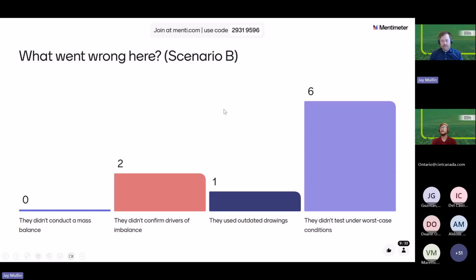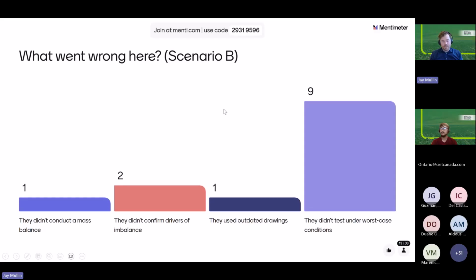All right, so we've got some suggestions coming in here. We've got a couple of answers that they didn't confirm the drivers of imbalance. That's possible. There were things like the broken dampers and stuff like that. There could have been other things going on that weren't the real problem. But it looks like most of the people are answering here that they didn't test under the worst case conditions.